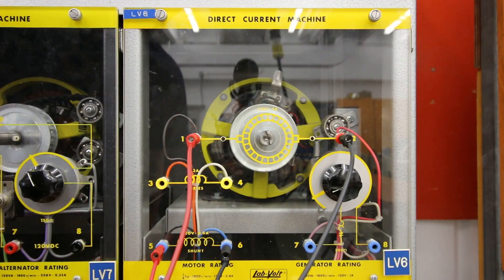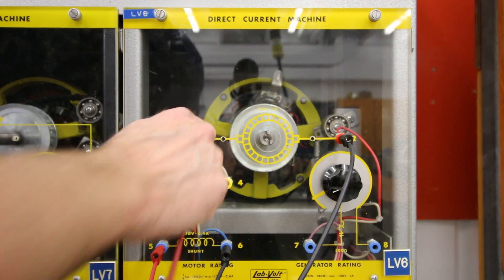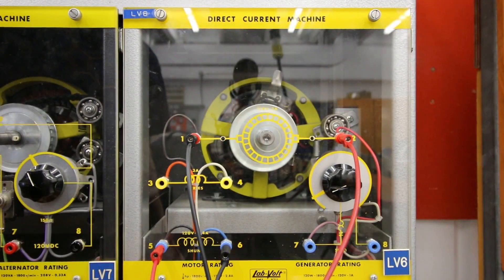If I want to get this guy to go in the opposite direction, all we have to do is just switch our A1 and A2 for our armature, and it goes in the opposite direction.